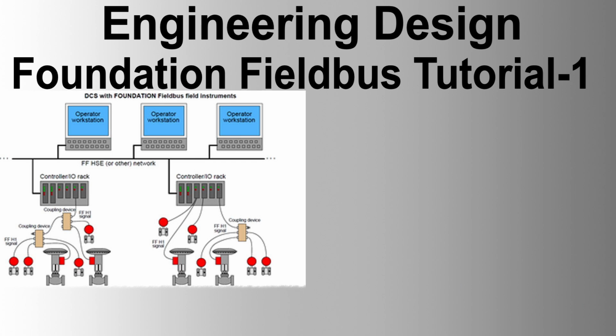Signaling method. Fieldbus utilizes a similar technology for smart transmitters to transmit an electric signal to the wire. The supply voltage is applied by a power supply through an impedance conditioner, typically consisting of inductors. DC current through the impedance conditioner feeds devices. The impedance conditioner makes the output impedance of the power supply higher than 400 ohms in the signal frequency bandwidth. Each cable end is terminated with a terminator of 100 ohms impedance. It makes an instrumentation cable a balanced transmission line so that a signal of relatively high frequency can be transmitted with a minimum distortion.